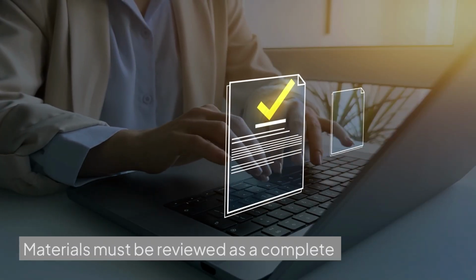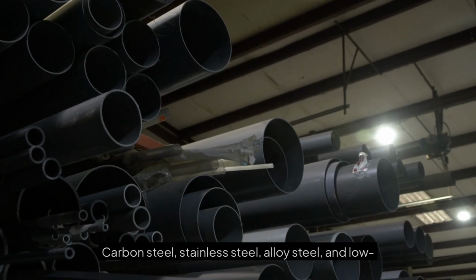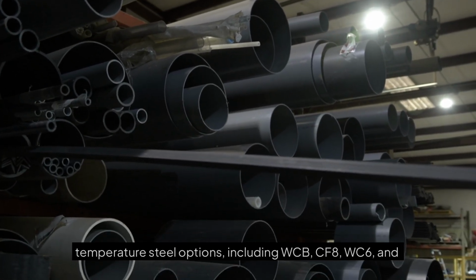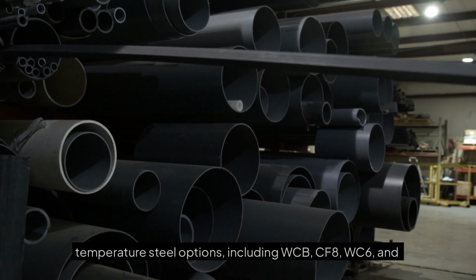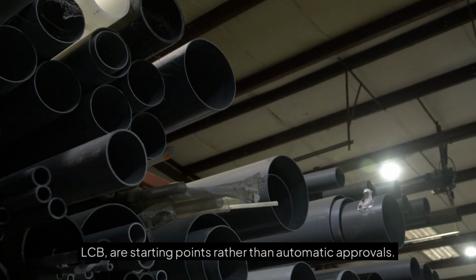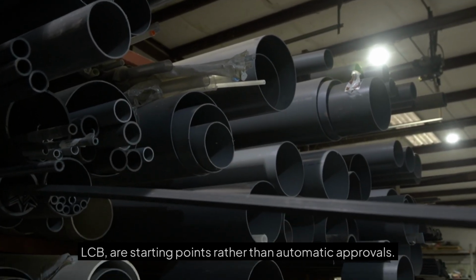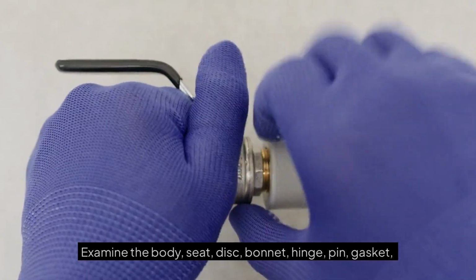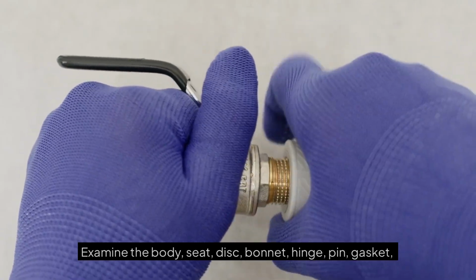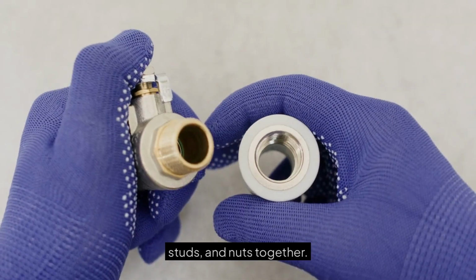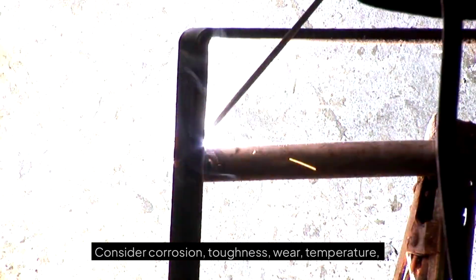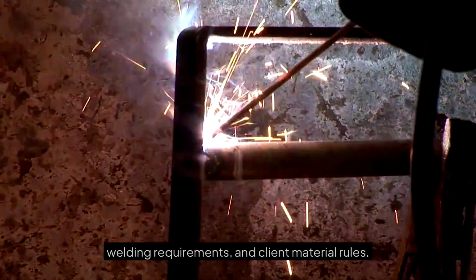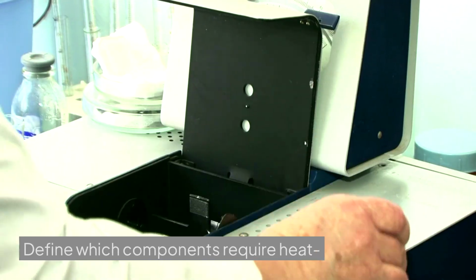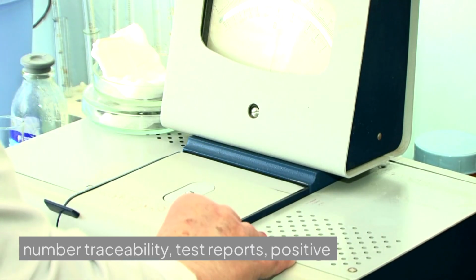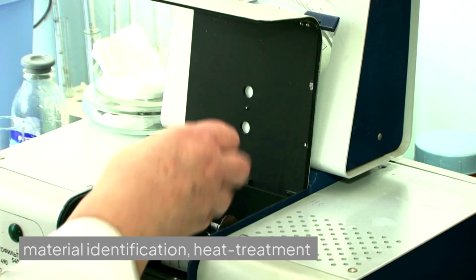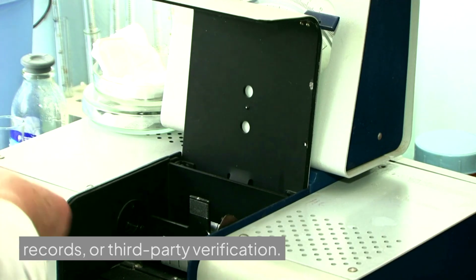Materials must be reviewed as a complete system. Carbon steel, stainless steel, alloy steel, and low-temperature steel options, including WCB, CF8, WC6, and LCB, are starting points rather than automatic approvals. Examine the body, seat, disc, bonnet, hinge, pin, gasket, studs, and nuts together. Consider corrosion, toughness, wear, temperature, welding requirements, and client material rules. Define which components require heat number traceability, test reports, positive material identification, heat treatment records, or third-party verification.